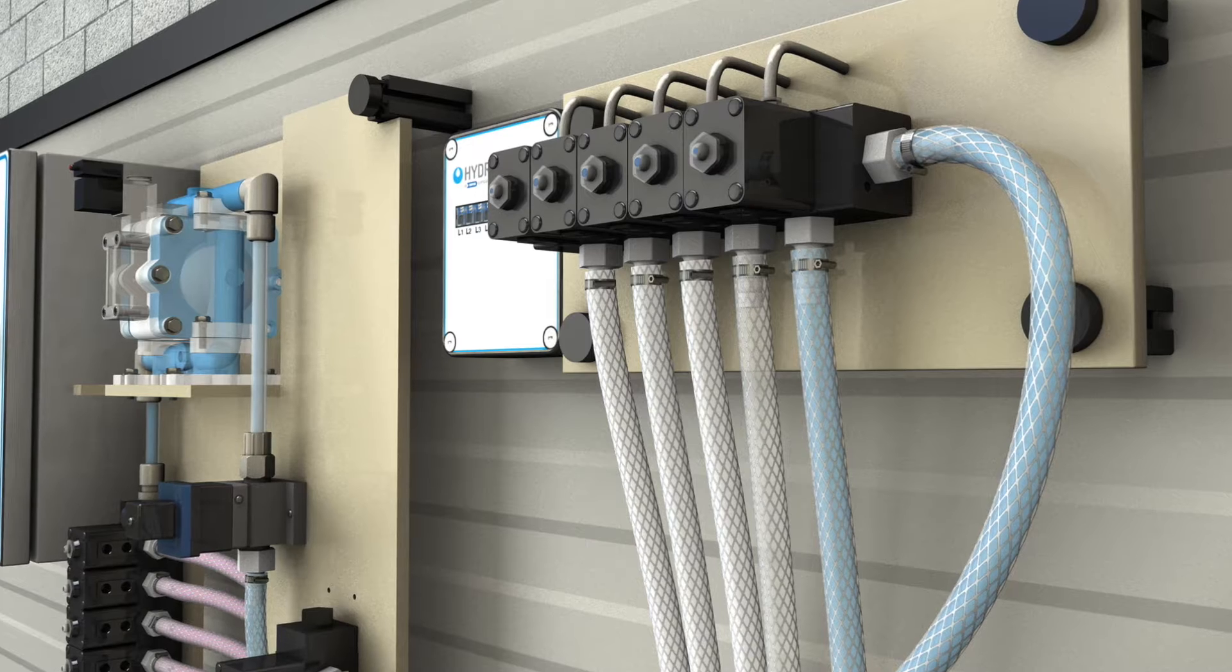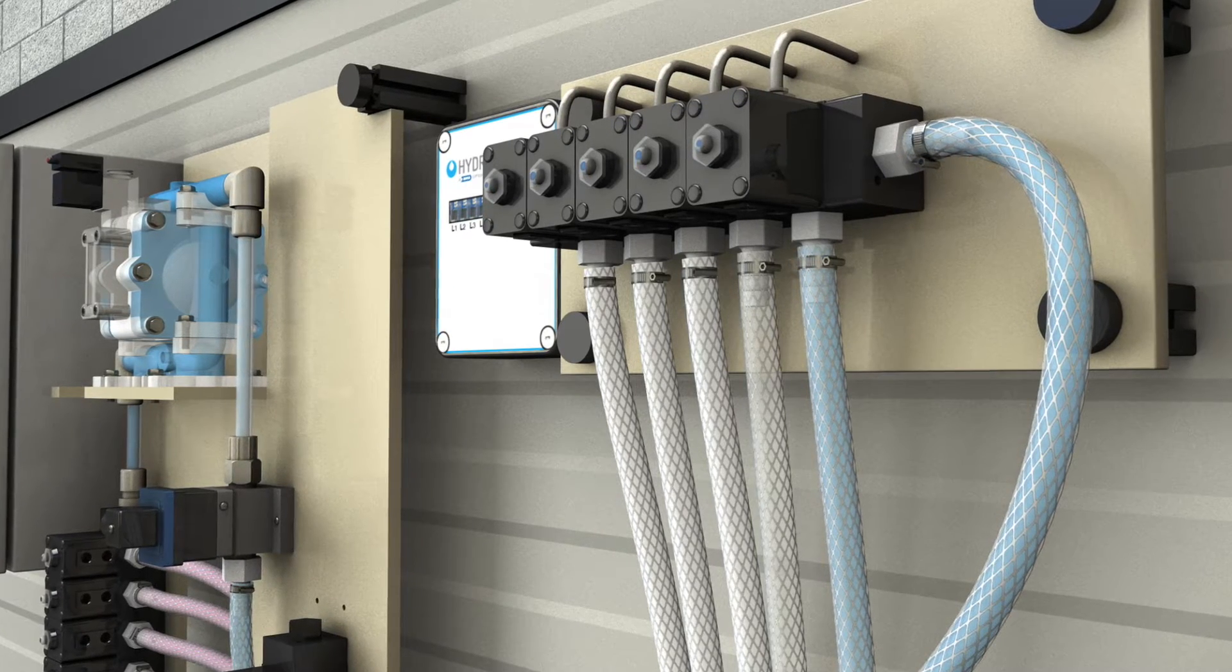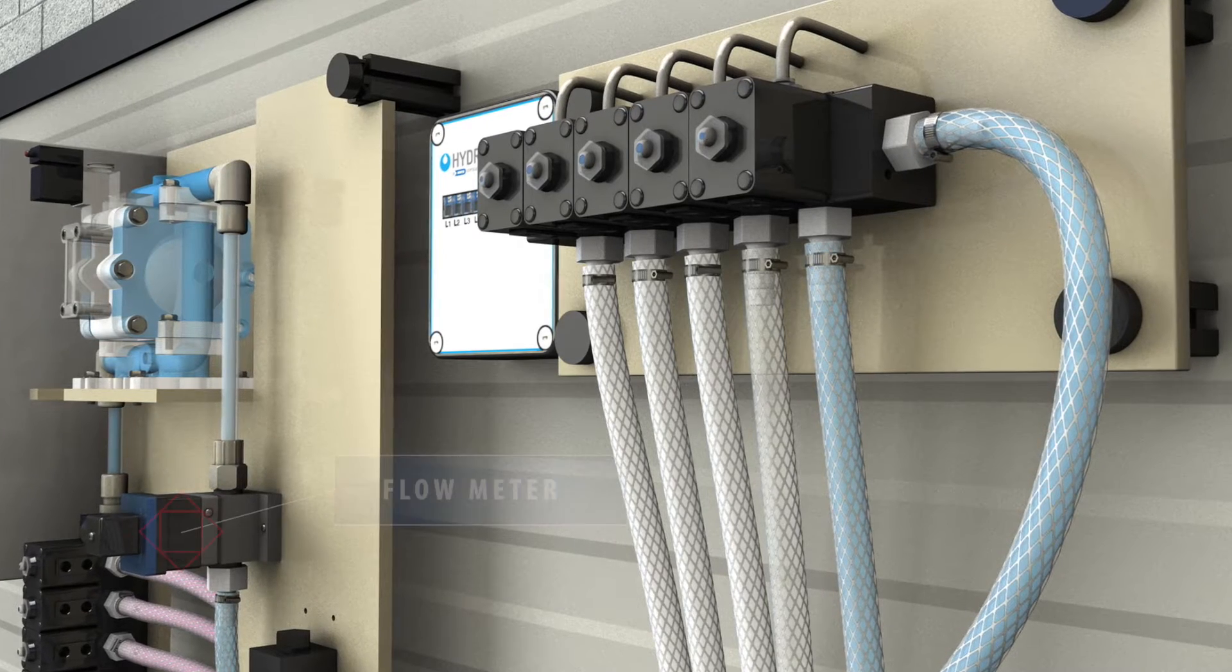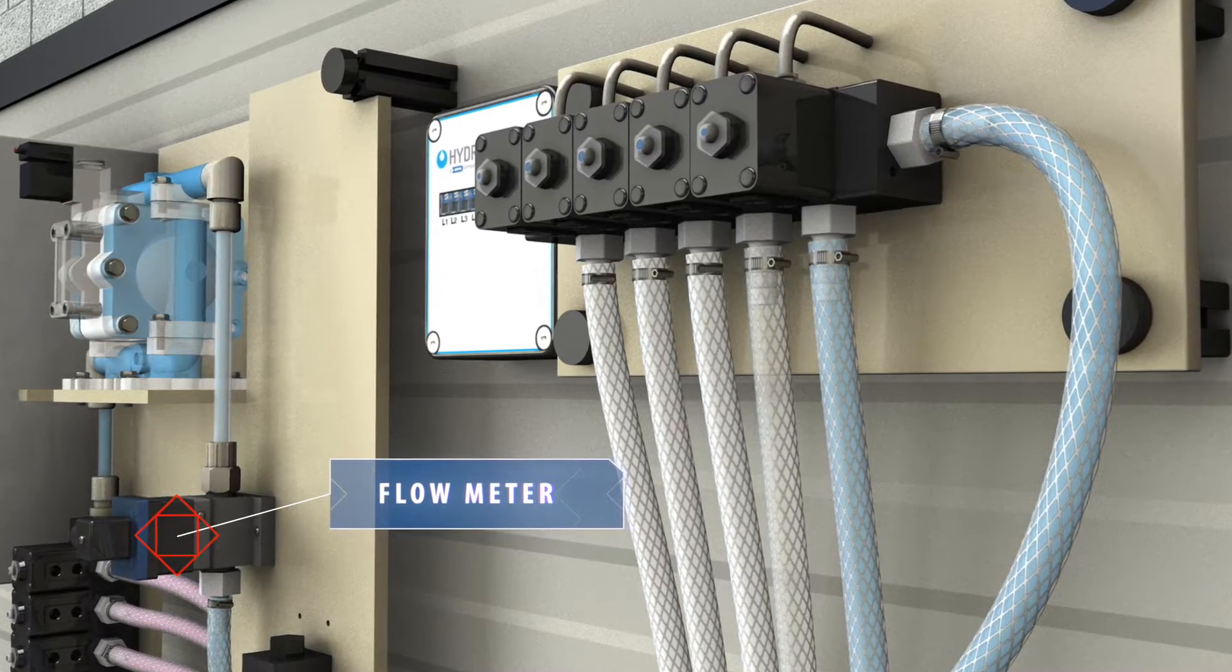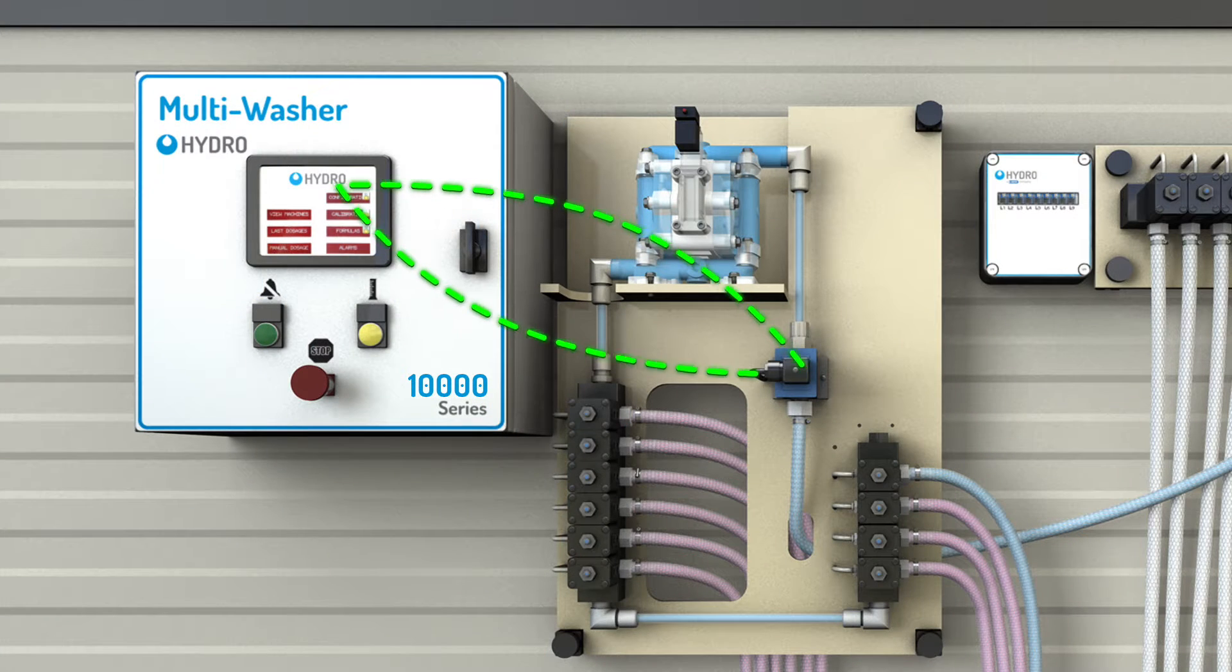The water test will verify there's sufficient water flow through the dosing channel to ensure the chemical when pumped can be flushed to the washer. As water passes through the flow meter, highly accurate pulse signals are detected by the PLC indicating the volume of water passing through the meter. If the PLC detects the correct number of pulses from the flow meter, the test is considered passed.